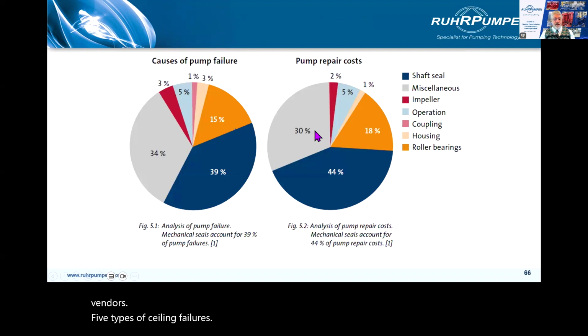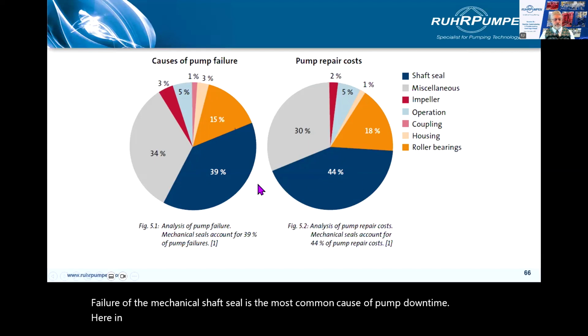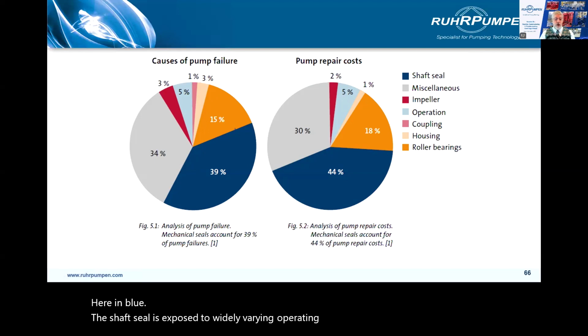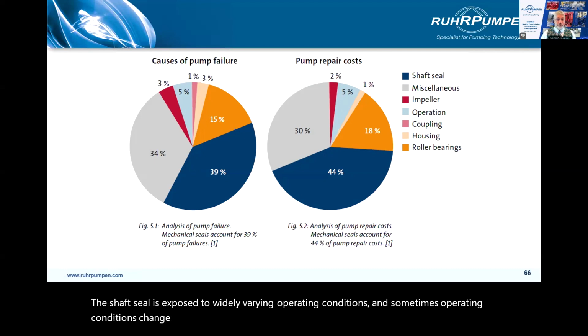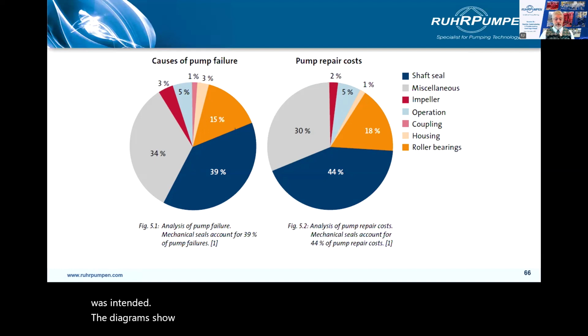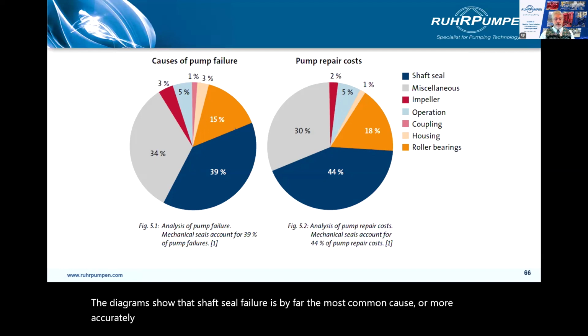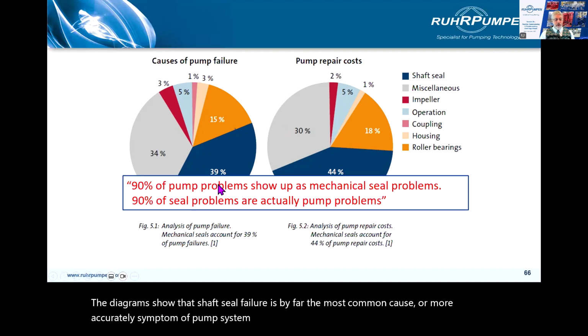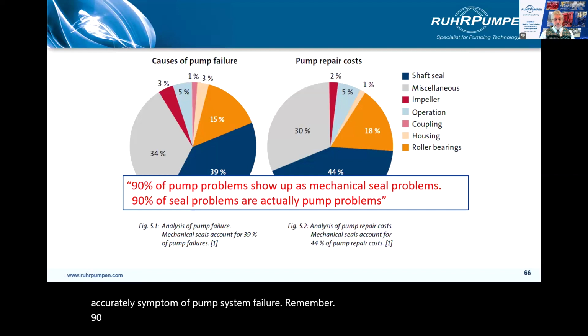Failure of the mechanical shaft seal is the most common cause of pump downtime, here in blue. The shaft seal is exposed to widely varying operating conditions, and sometimes operating conditions change to become quite different from the specific conditions for which the seal was intended. The diagrams show that shaft seal failure is by far the most common cause, or more accurately, symptom of pump system failure. Remember, 90% of pump problems show up as mechanical seal problems, but 90% of seal problems are actually pump problems.